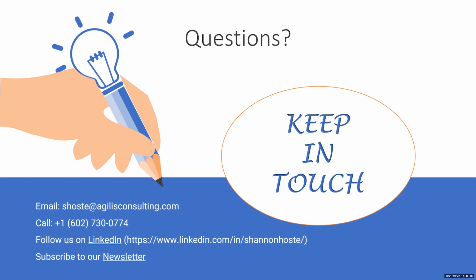Yeah, that's a tough one for usability. So the challenge there is, one, the FDA flat out in the guidance asks for U.S. data. That's the populace they're in charge of protecting the public health for, and they're looking to make sure, because as you're testing user groups, are there any differences between those user groups in different countries that could affect performance with the device, for example?